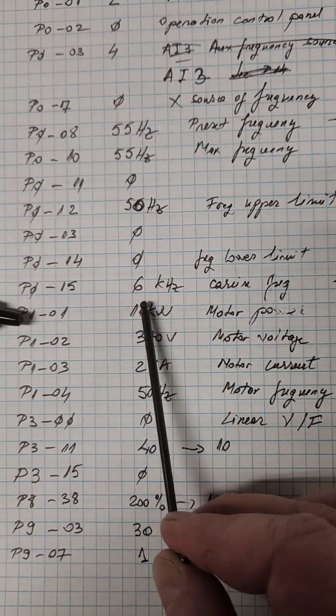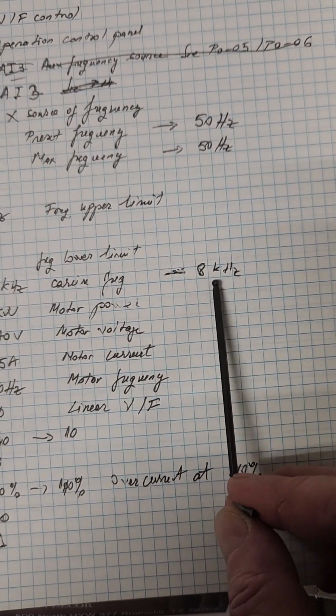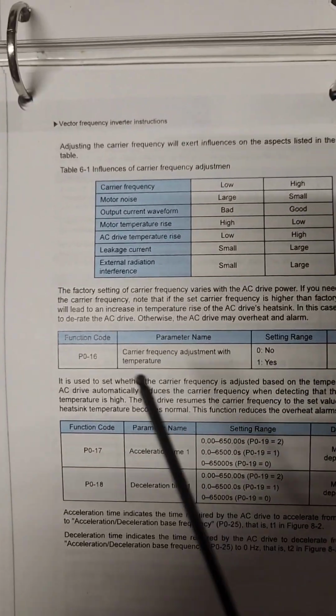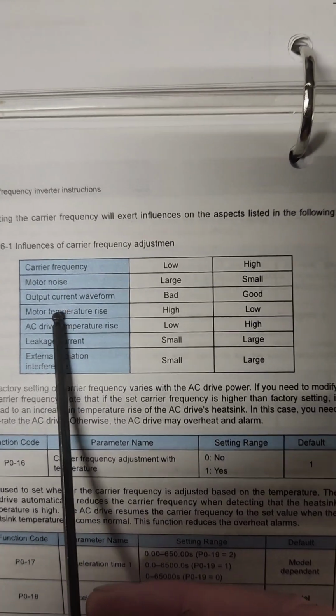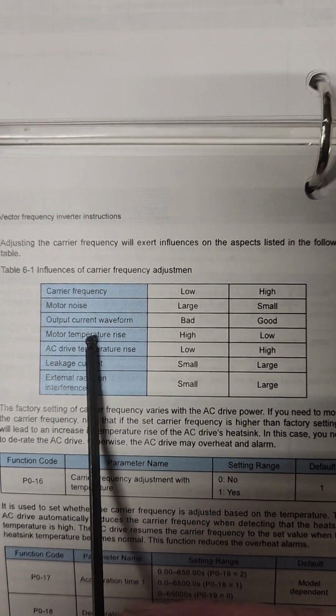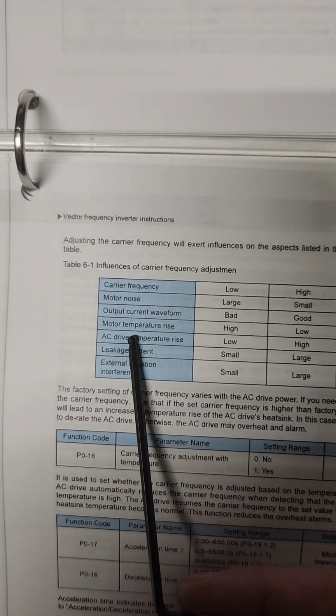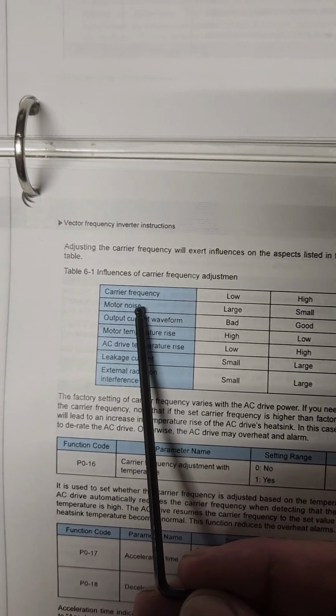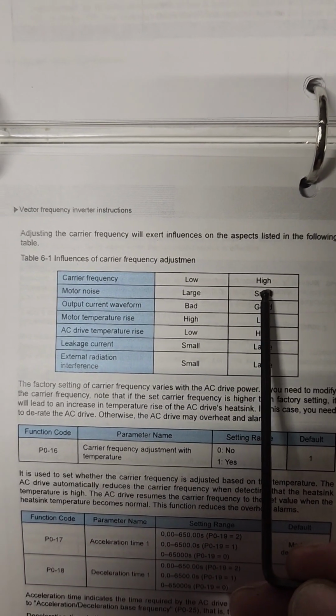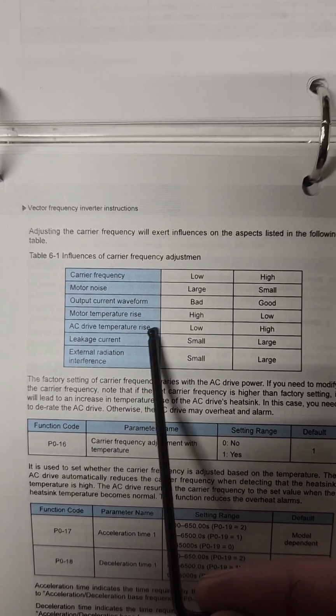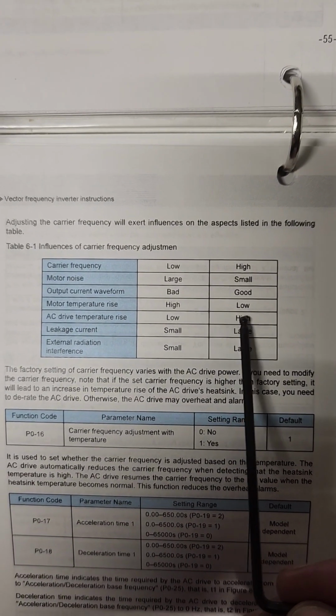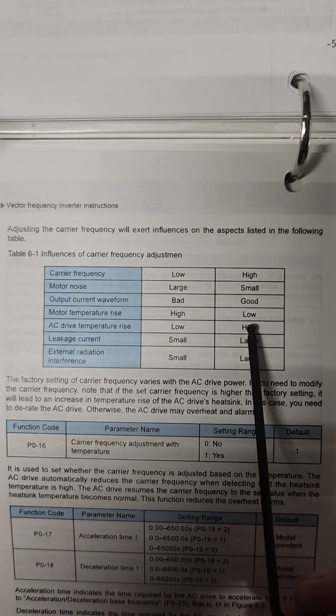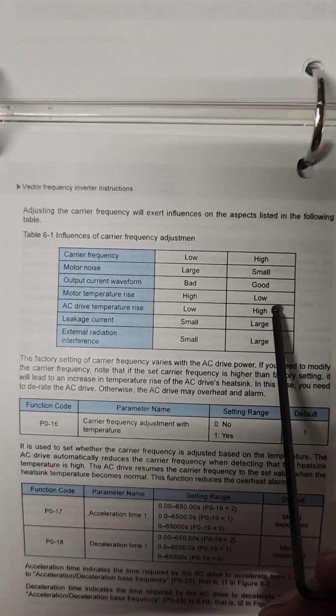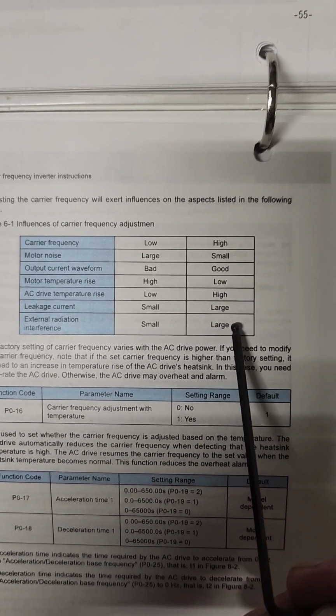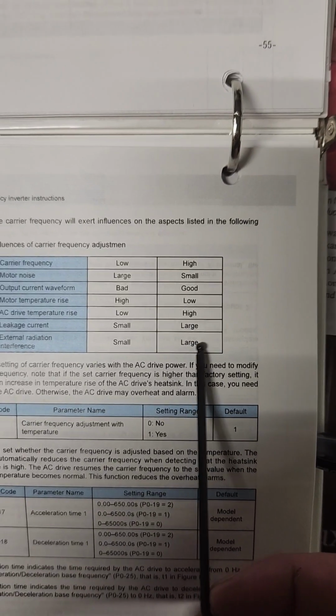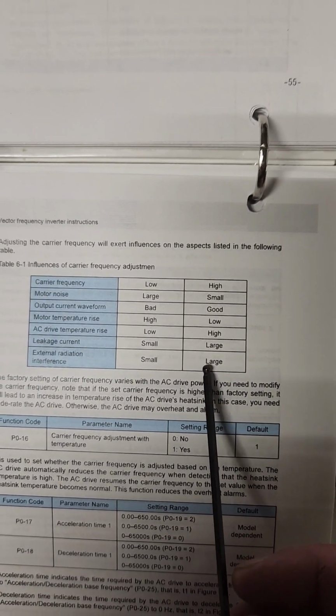These two I changed from 55 to 50 Hertz. And the carrier frequency was 6 kilohertz like we saw on oscilloscope. I changed that to 8 kilohertz. And here's an explanation they provide based on the carrier frequency. I don't have a motor here, I'm driving the Spindle Servo driver, but what we see here, noise, right? The noise in the motor, or what follows the inverter, it's small at high frequency, but the drive temperature will rise at high frequency because of the IGBT transistor switching, and there is interference radiation created on the line back to the mains, right, back to 240 volts. So we're gonna look at that.